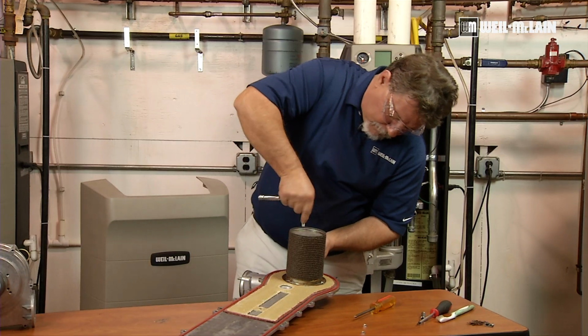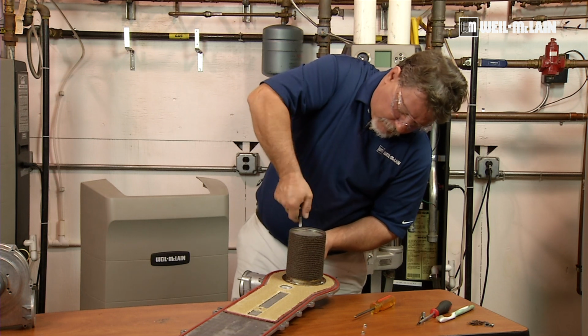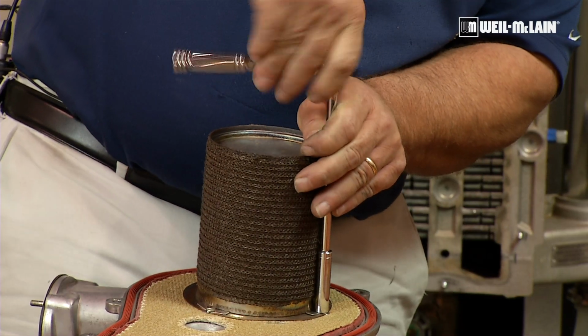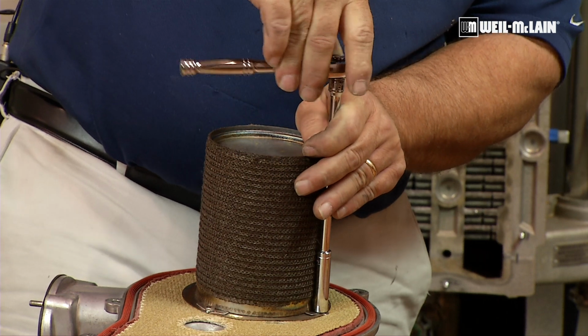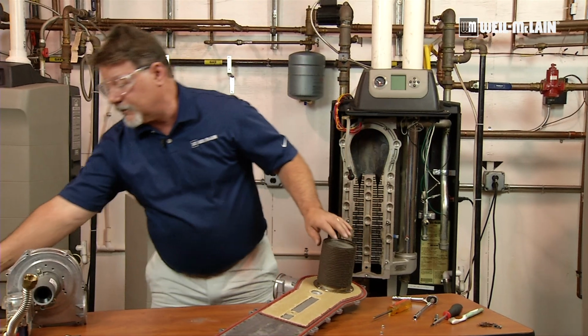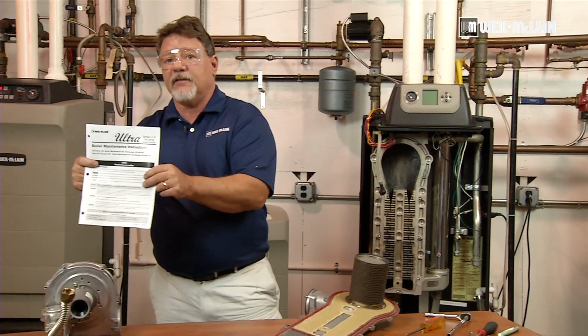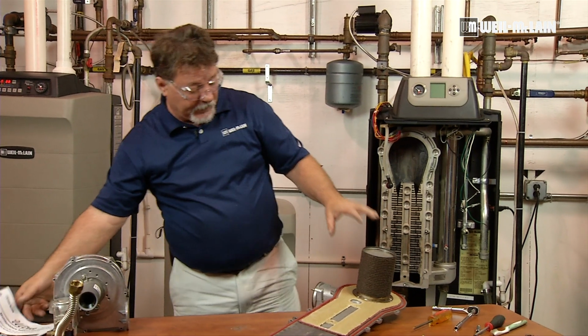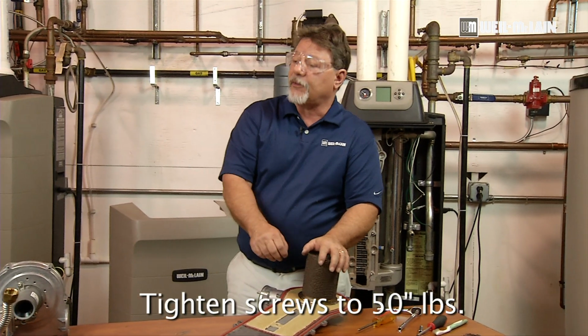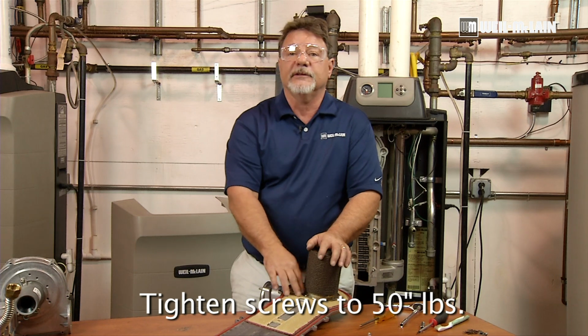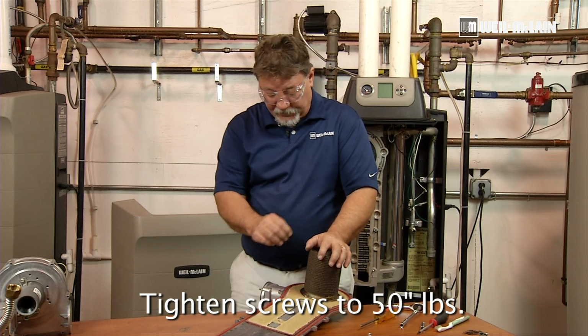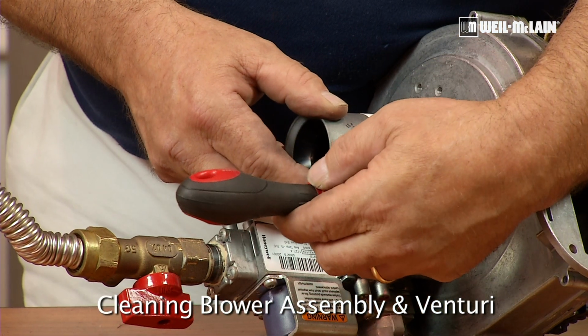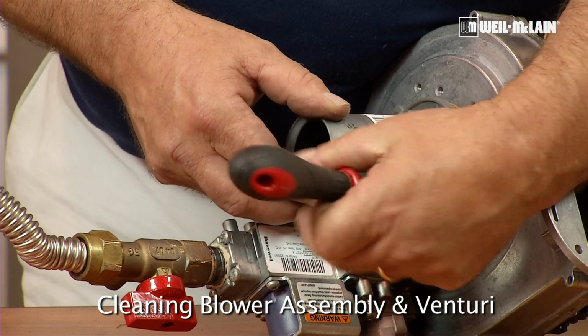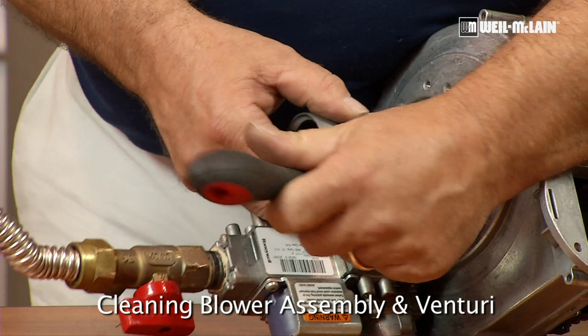Repeat that process until all burner bolts have been reinstalled. Now, following the tightening procedure described in the maintenance instructions, we need to get an inch-pound torque wrench and torque these down to 50 inch-pounds. We're going to take a number 20 Torx, and there's just a couple screws here that we're going to remove.